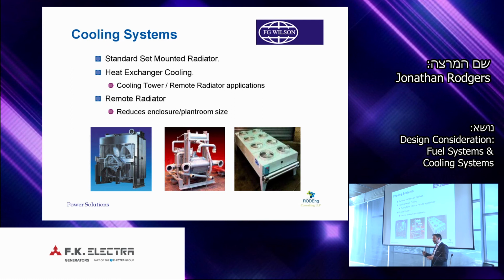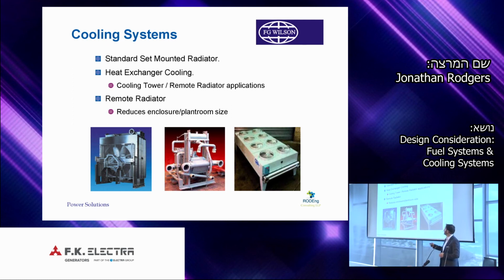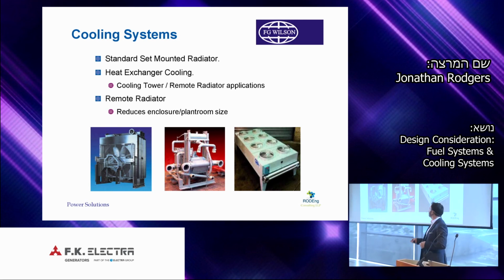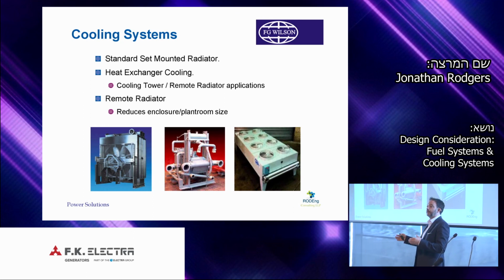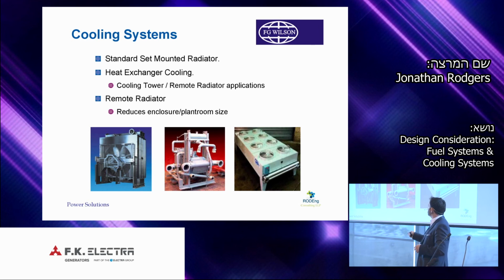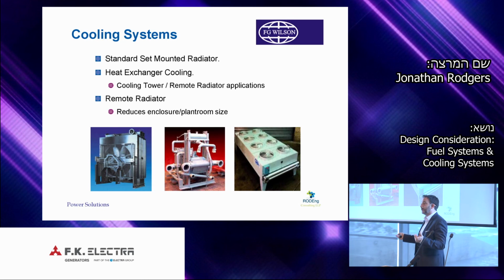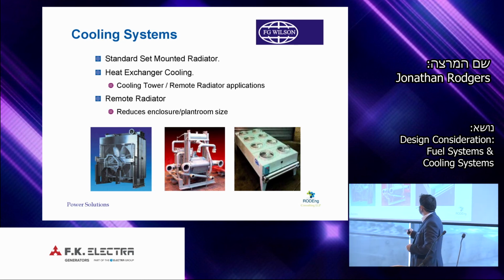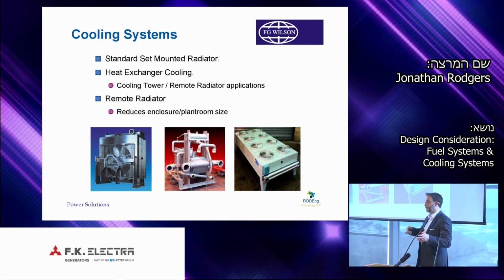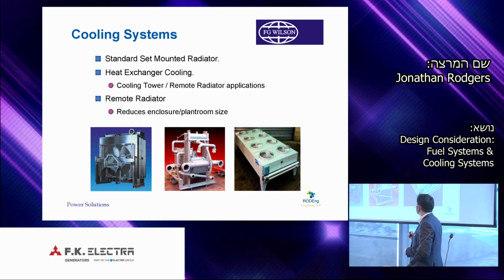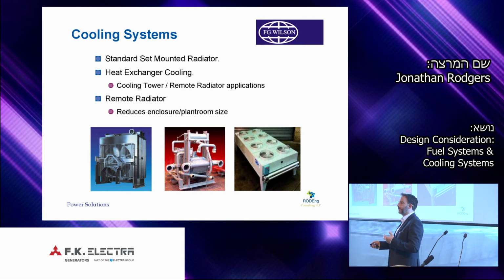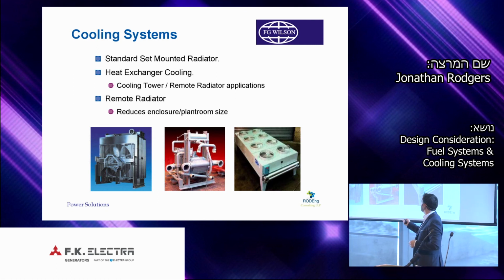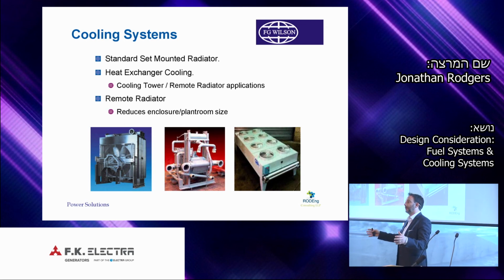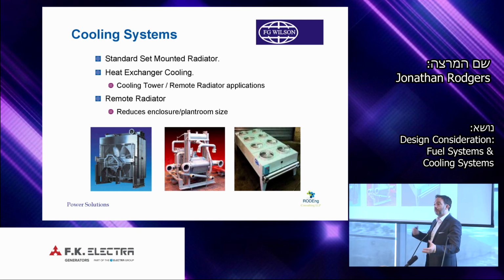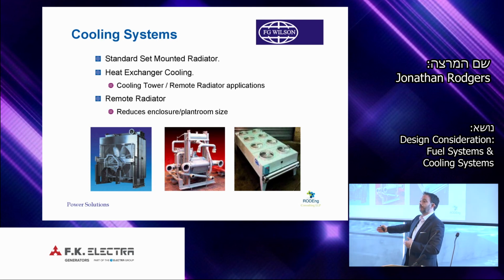These different configurations give us a variety of cooling platforms to use, but in effect they all are providing the same function, and with the function we have similar options for different applications. Our standard set mounted cooling is a radiator, as we say it, maybe single circuit, or it might be a twin circuit. Then we can have heat exchanger selections, where the heat exchanger will be sized for charge and jacket waters, or charge air and jacket water. But these will be supplied as a package with the generator. And what happens is then we look at the expansion vessel, the sizing of the header tank, the deaeration lines, the venting. That's all catered for on the generator package with its remote cooler. And then there may be remote radiators to be used, so a radiator in another location from the generator.